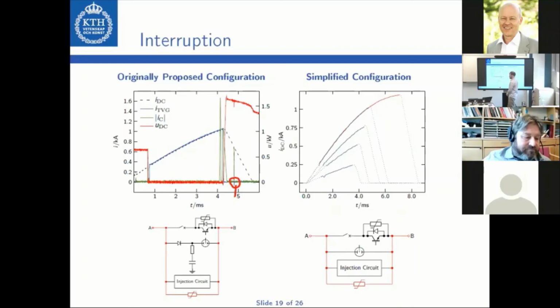I don't expect this, and I can clearly say why. First of all, you know the ratings of these devices, so this is just 1.6 kilovolts, so it is very unexpected if a breakdown should already occur at this kind of voltage. The other aspect is that we have conducted these experiments before with a solid state breaker, when we initially tested the advanced test circuit, and then the same kind of spikes appeared, even more frequently. The later one is a very good argument. The first one—there are reasons why you might see reignitions or restrikes in a device with high ratings as well, which clear themselves after a very short time.